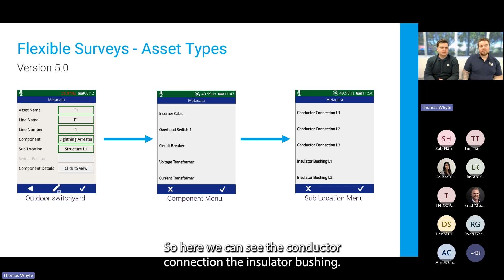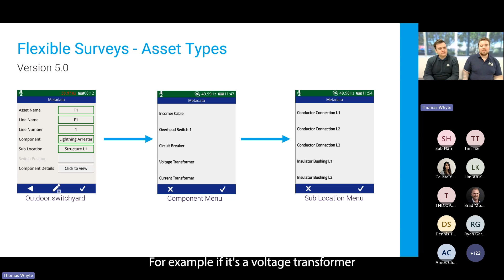And so now you'll see that the switch position is blanked out, and you now have a sublocation. This directly relates to what part of that component you were testing. So here we can see the conductor connection, the insulator bushing. The sublocation menu will change depending on what component is selected — for example, if it's a voltage transformer, there'll be a tank, whereas a lightning arrestor would not.